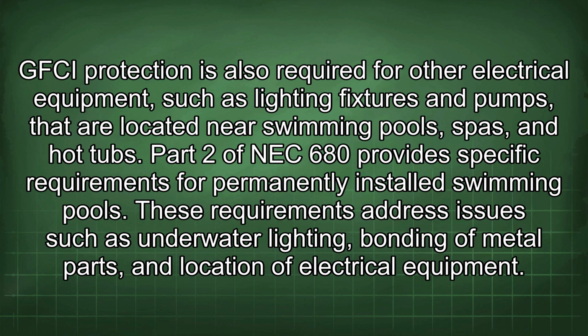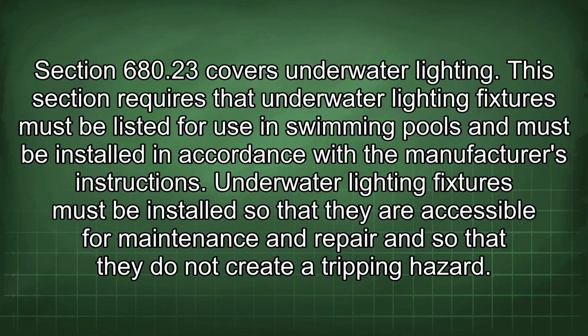Part 2 of NEC 680 provides specific requirements for permanently installed swimming pools. These requirements address issues such as underwater lighting, bonding of metal parts, and location of electrical equipment. Section 680.23 covers underwater lighting. This section requires that underwater lighting fixtures must be listed for use in swimming pools and must be installed in accordance with the manufacturer's instructions. Underwater lighting fixtures must be installed so that they are accessible for maintenance and repair and so that they do not create a tripping hazard.